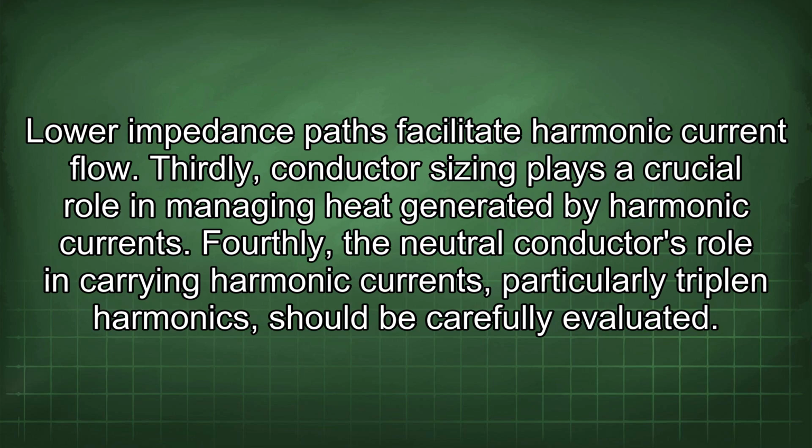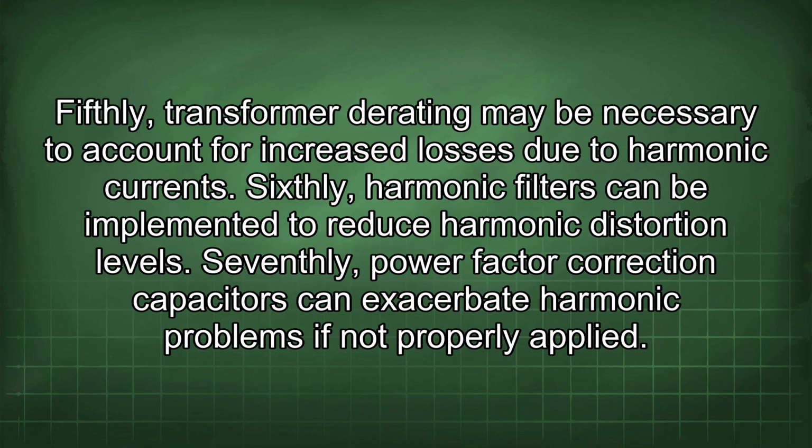Thirdly, conductor sizing plays a crucial role in managing heat generated by harmonic currents. Fourthly, a neutral conductor's role in carrying harmonic currents, particularly triplen harmonics, should be carefully evaluated. Fifthly, transformer derating may be necessary to account for increased losses due to harmonic currents. Sixthly, harmonic filters can be implemented to reduce harmonic distortion levels.